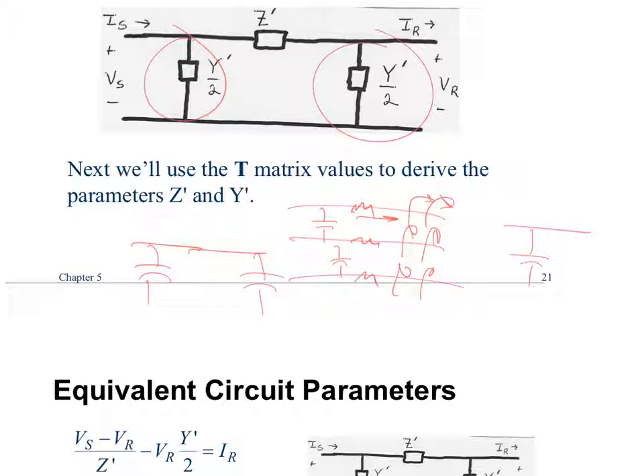Is there a difference between capacitance between the lines and capacitance to ground? It's usually modeling the capacitance between the lines. Capacitance to ground usually affects the zero sequence capacitance. But that still does impact the overall capacitance, because you have something called line charging. If you just energize a line without running any current through it, you still get some capacitance there because the voltage is present.